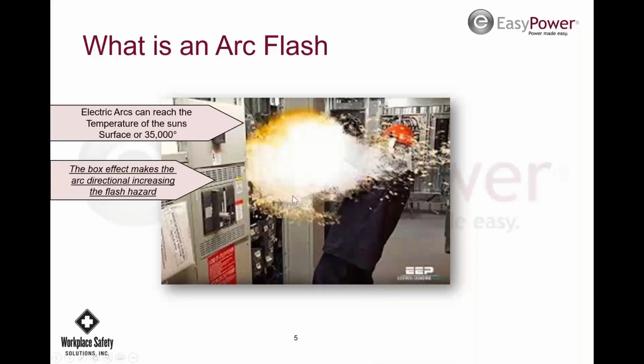The box effect is about 10 times greater in a box like this, like you're seeing in the panels and things like that, than it would be in open air. So you don't see linemen with full suits on because it's 10 times less than it is. Plus the fault current is going to probably be less on the primary side of things than it is on the secondary side. So there's a few reasons, but OSHA does not require suit hoods and full suits for open air work.